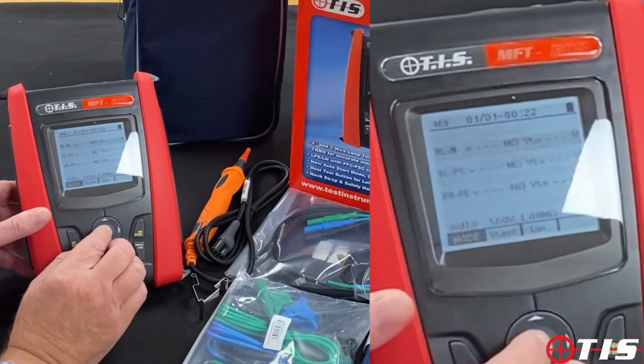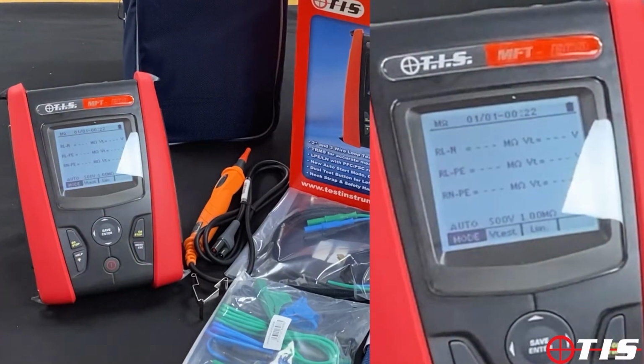Insulation test. Big advantage with this insulation tester, although it will do a single shot insulation test, we have put an automatic mode in here, which with one connection and one key press will allow us to do all of the insulation tests together. So it will do live neutral, live earth, neutral earth, all with one key press, display the results and also the voltages that were carried out on the circuit.